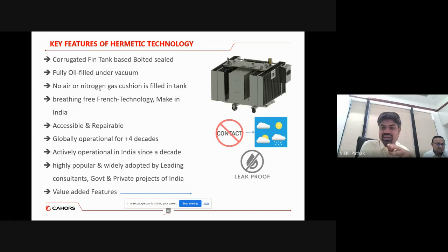10,000 plus transformers from our Indian factory, unless there is a force damage, we have not received any complaints about leakages, because we are exporting, as you have seen already, to different countries, and they are not so close, but very far. So in such cases, the product is very promising about conformity towards leak proofness, which we are testing on every transformer in our factory. Unless the quality department confirms the transformer is leak proof, it is not given to logistics for the dispatch process. Even if there is a small or minor or hair crack possibility of leakages, that is solved in the factory itself. We ensure that whichever product is delivered, in whichever state or country, will be a leak proof product.